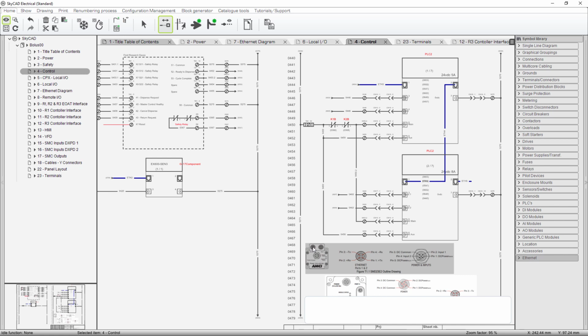So I can come in with an Ethernet cable from my Ethernet switch that's in the main panel, because this stepper motor is not in the panel. It's on the machine. It's on the fixture, the table. And then I can use another cable to come out of this Ethernet and go to this Ethernet connection, right there, this one. And I could jumper from this one, which I probably do, and go over to here. So I'm daisy chaining.